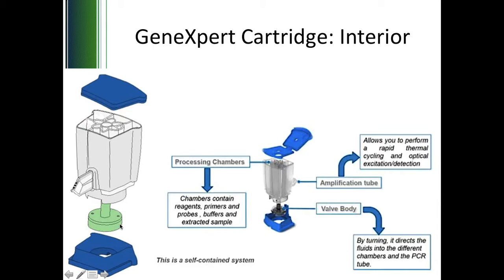So the entire cartridge works as a self-contained system. We need not do anything, just the sample is to be added. The cartridge will carry out RT-PCR and qPCR on its own, and no reagents are to be added. A fully automated, fully self-contained system.